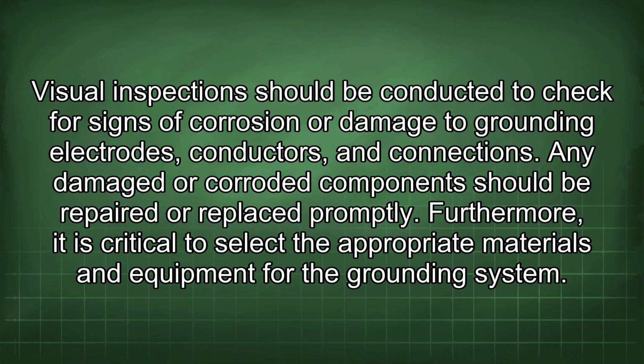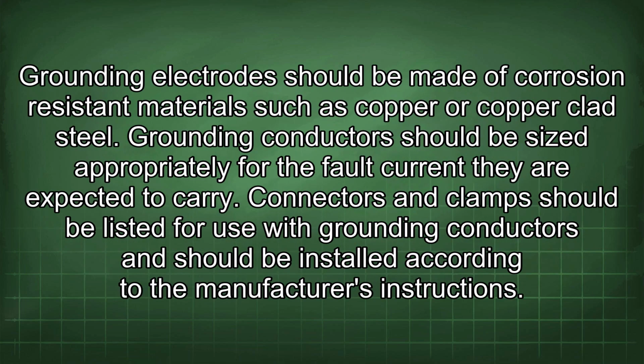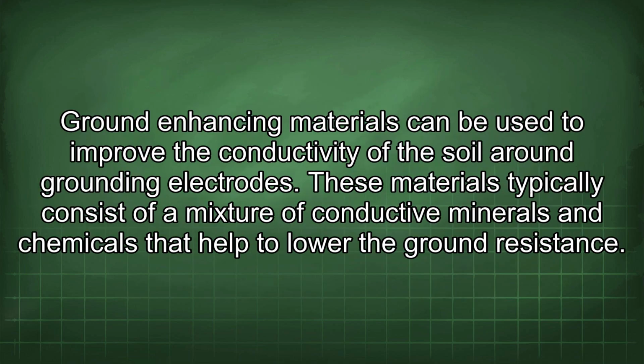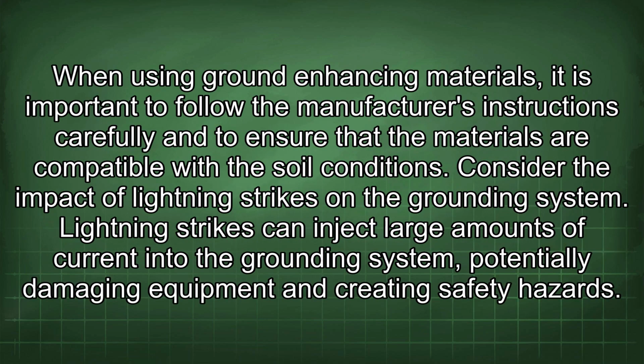Furthermore, it is critical to select the appropriate materials and equipment for the grounding system. Grounding electrodes should be made of corrosion-resistant materials such as copper or copper-clad steel. Grounding conductors should be sized appropriately for the fault current they are expected to carry. Connectors and clamps should be listed for use with grounding conductors and should be installed according to the manufacturer's instructions. Ground-enhancing materials can be used to improve the conductivity of the soil around grounding electrodes. These materials typically consist of a mixture of conductive minerals and chemicals that help to lower the ground resistance. When using ground-enhancing materials, it is important to follow the manufacturer's instructions carefully and to ensure that the materials are compatible with the soil conditions.